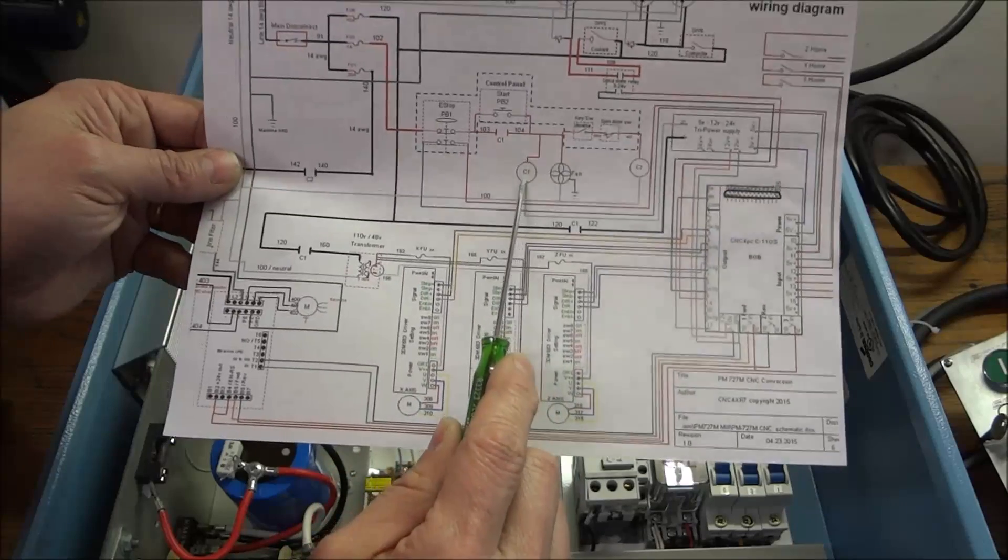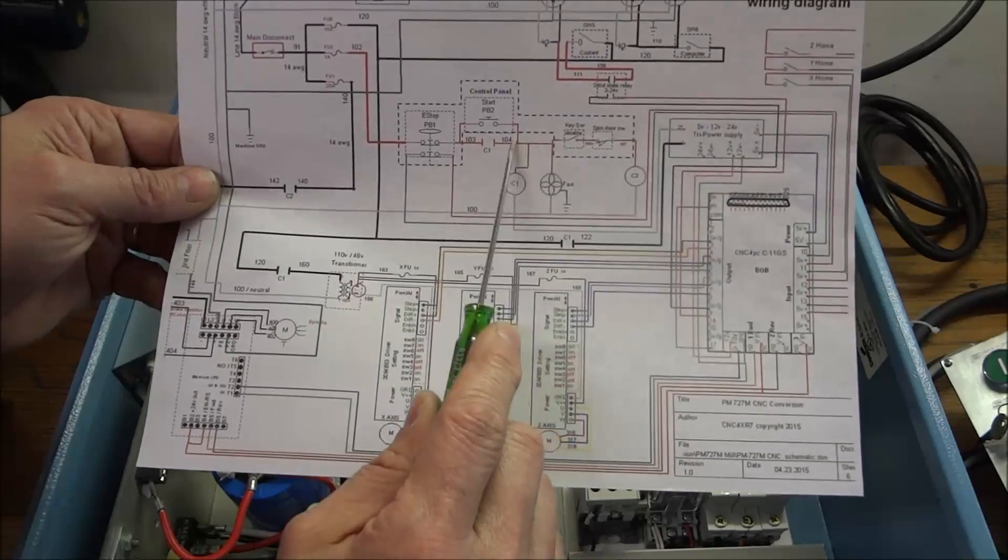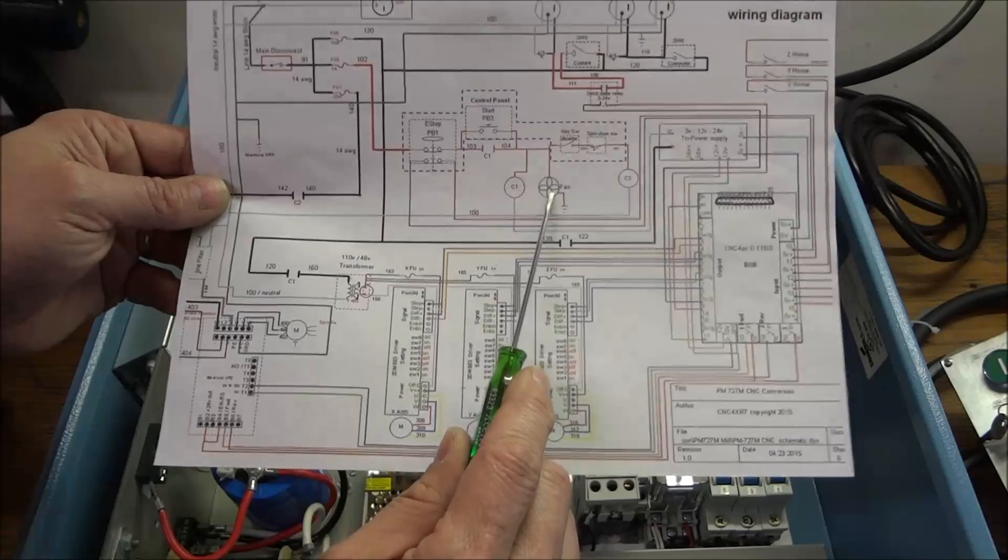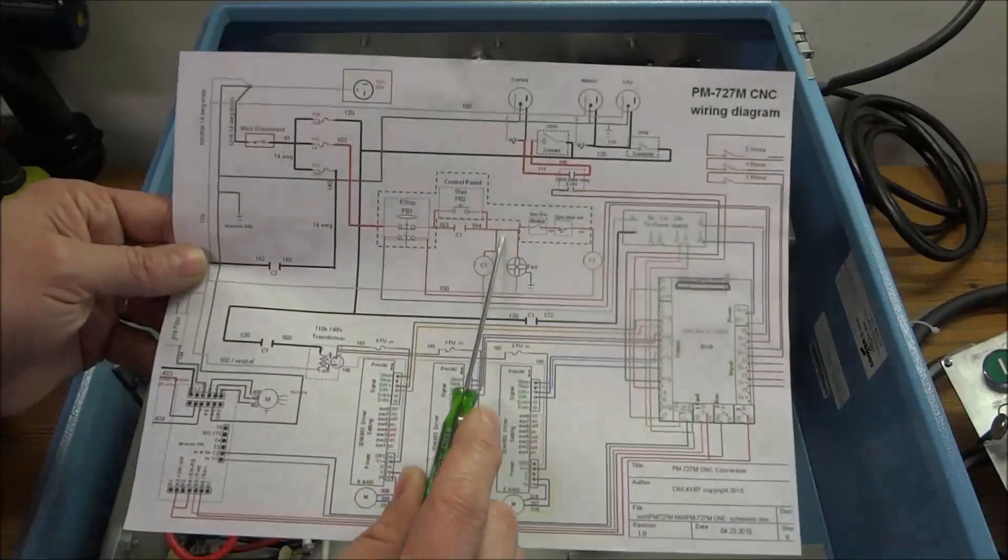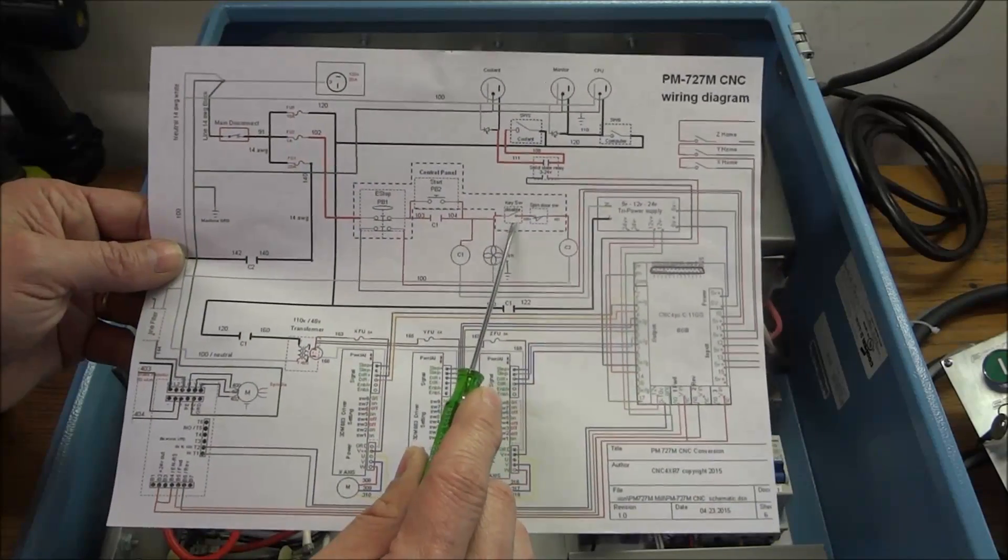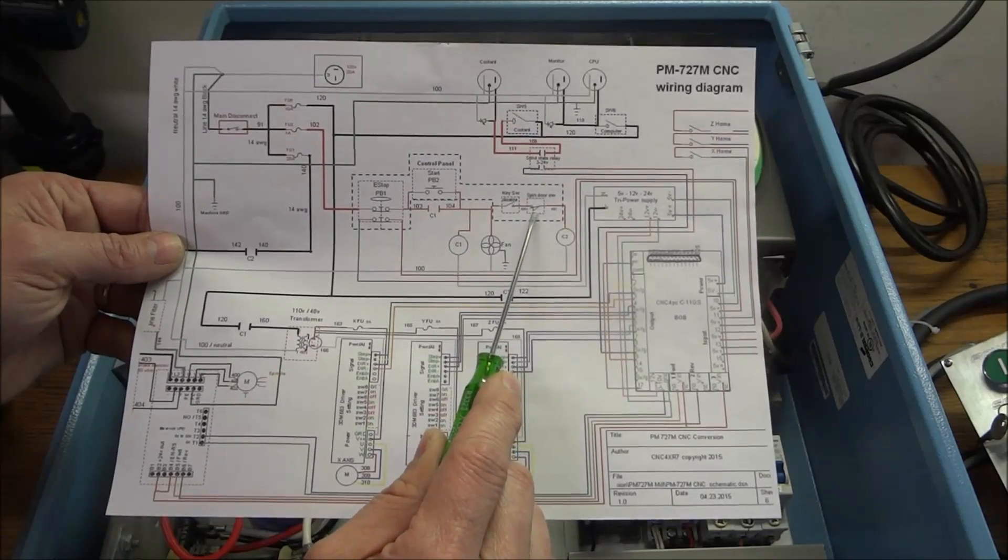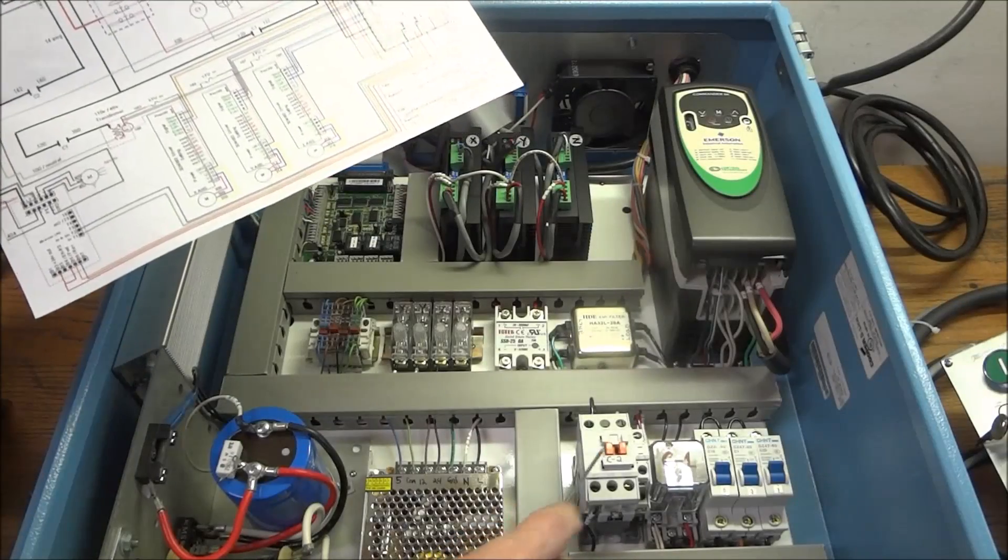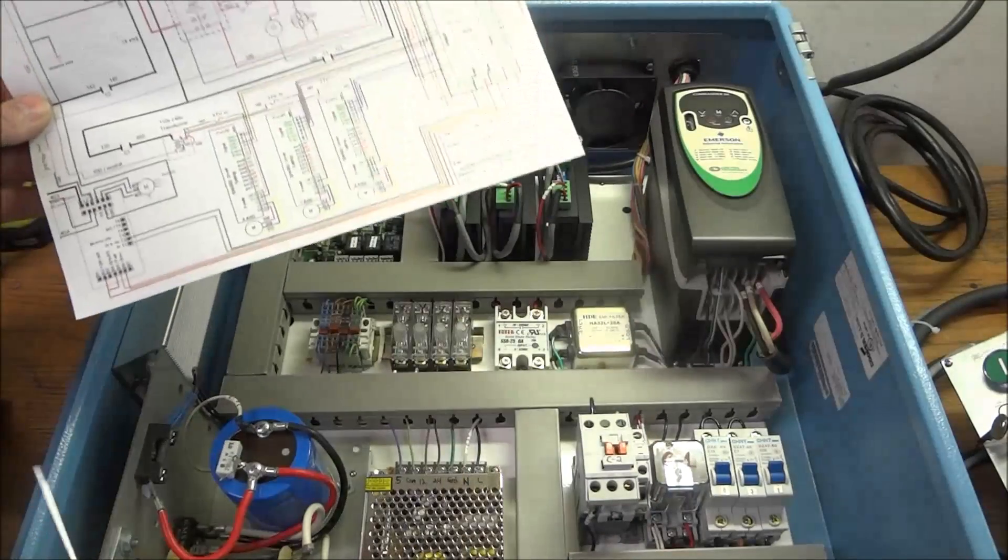After C1 contactor is pulled in, the fan will come on and also if the key switch is turned and the door switch is closed, it will also energize C2 contacts for our big contactor and power will be applied to our VFD.